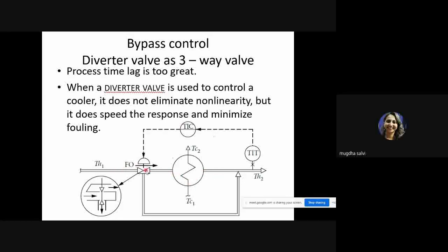So what we are doing is, now this is temperature TH1. Everything is going on fine. TH2 is being maintained at its set point. Suppose by any reason this temperature TH2 drops below the set point. Since there is no control over the cold fluid, what option do I have? One option is I start opening this control valve. The moment I open it more, there will be more liquid flowing through at a higher flow rate, and again TH2 will come back to its set point.